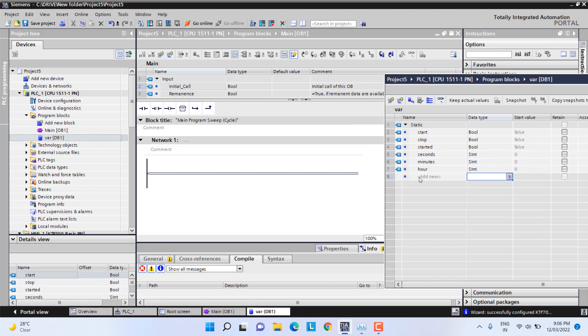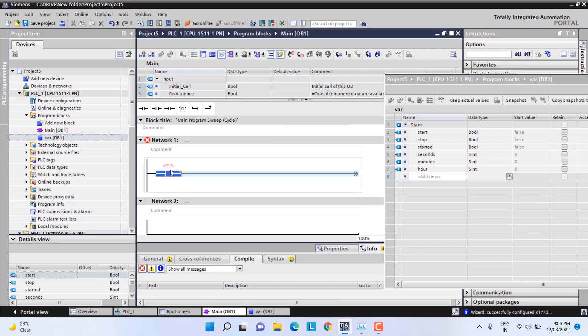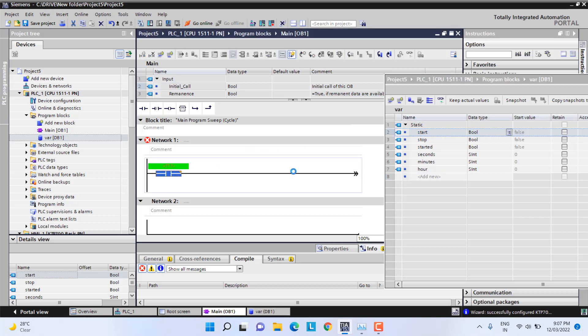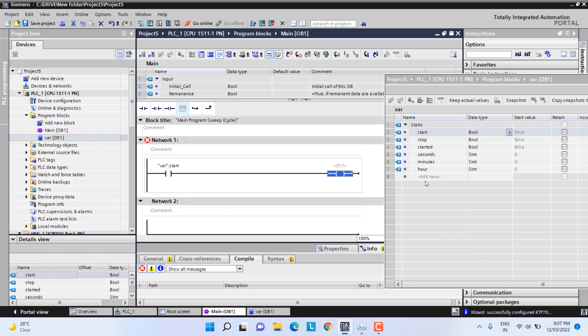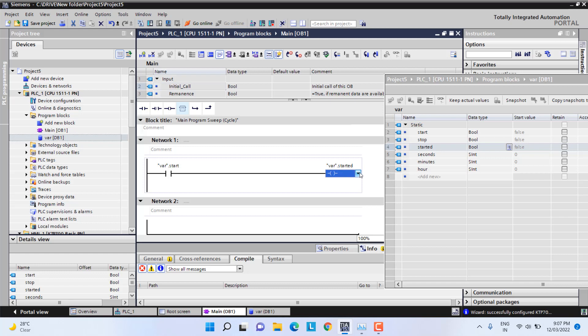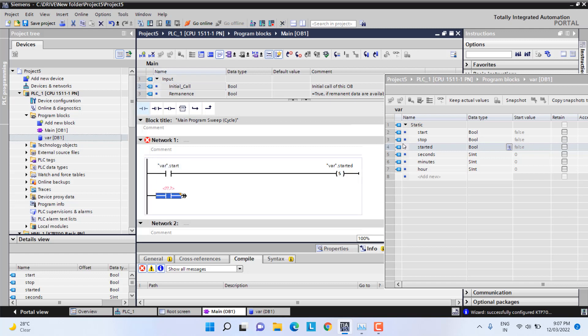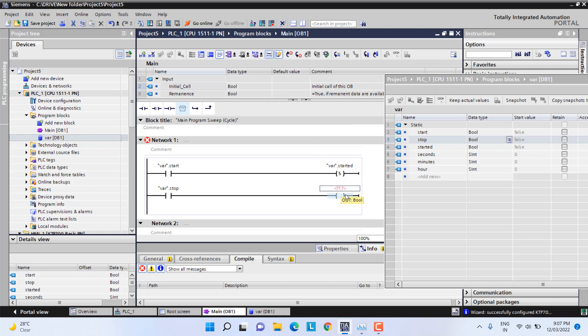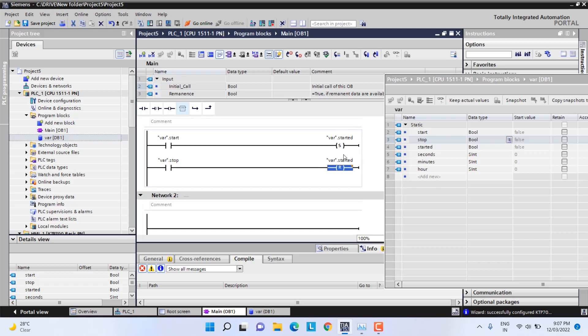First we will make the start button logic — this will be our start button and we will set that bit here. We already created that bit, so we will make it a set bit. Then we will make one branch here and this will be the stop. If you press stop, it has to reset this bit. So I will copy here and it will be reset. Once we press start, this bit will be set from the HMI start button, and this will be the stop from the HMI.